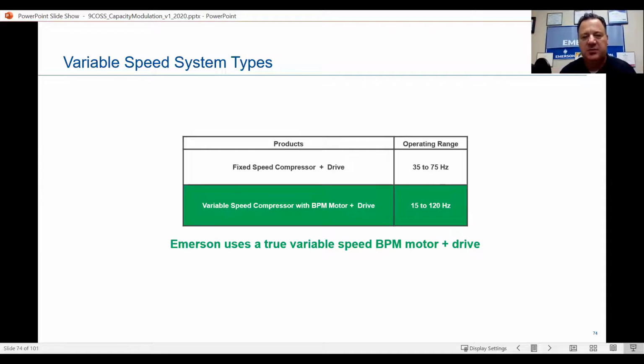We stayed out of this variable speed market for a long time for fear of lubrication. All of our scrolls, with the exception of the variable speed, all run 3,500 RPMs. We like that because we lubricate by that shaft coming up in the scroll. This actually has a pump built into it at the bottom. So if that's ever a trick question on a test somewhere, you'll know that. Variable speed compressors with BPM, brushless permanent magnet motor, plus a drive will range from 15 to 120 hertz. Emerson uses a true variable speed BPM motor plus drive.